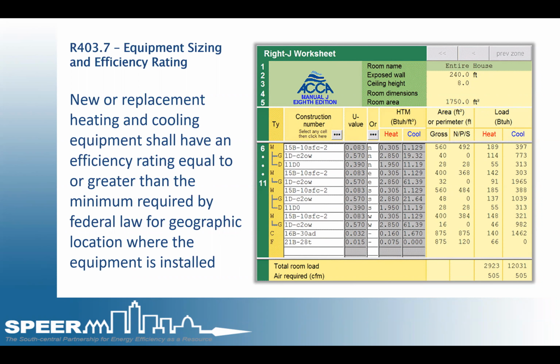Please do not only allow the AHRI to verify correct sizing. I've seen that a lot with builders. They turn in an AHRI certificate hoping to pass that. A few cities in Texas are already requiring Manual J and Manual S documents to be submitted with permit requests. If your city is not currently doing so, you should seriously consider it. This not only assures the correct size of equipment is being used, but it also almost guarantees the homeowner will be more comfortable and less energy is used to condition the homes.